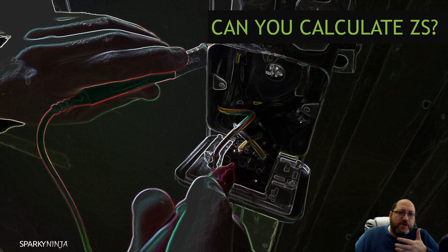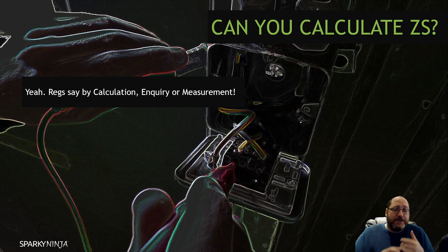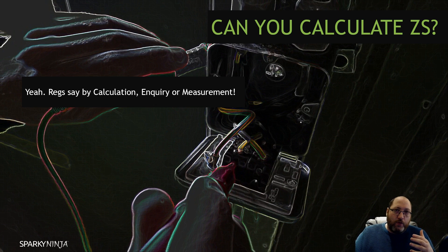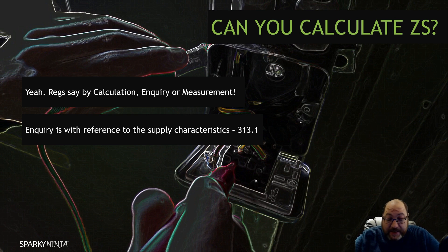The common response is: yes, you can calculate it because the regulations say we can obtain it by calculation, inquiry, or measurement. Well, that's only for — the inquiry is only for supply characteristics, so the ZE and PFC. So we can't inquire a ZS measurement; we just can't do that.